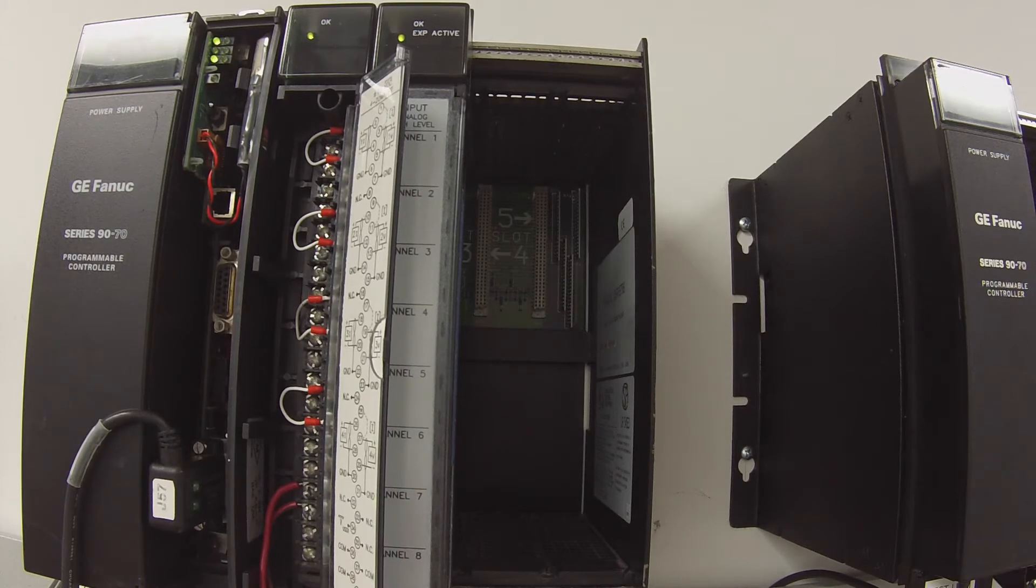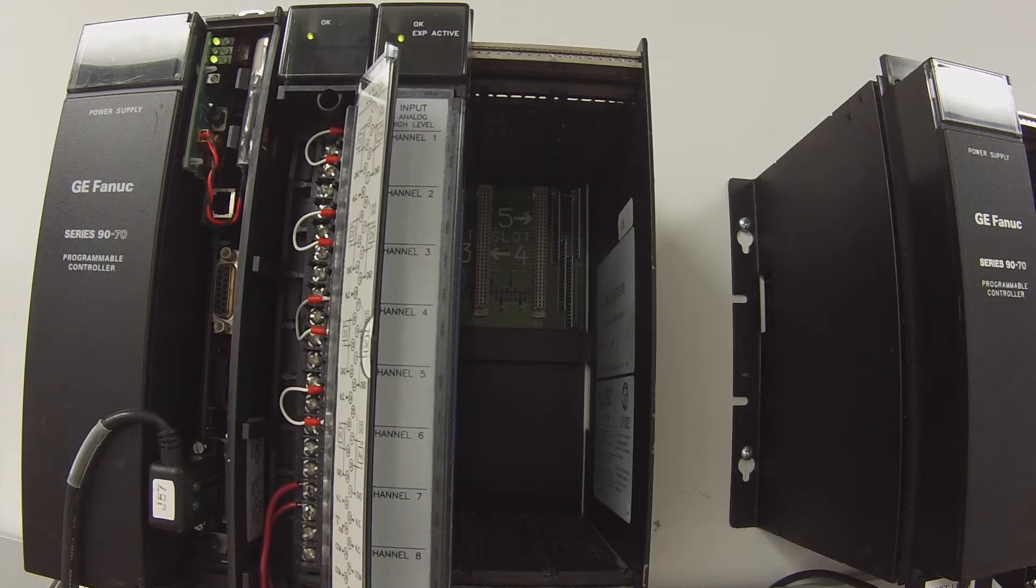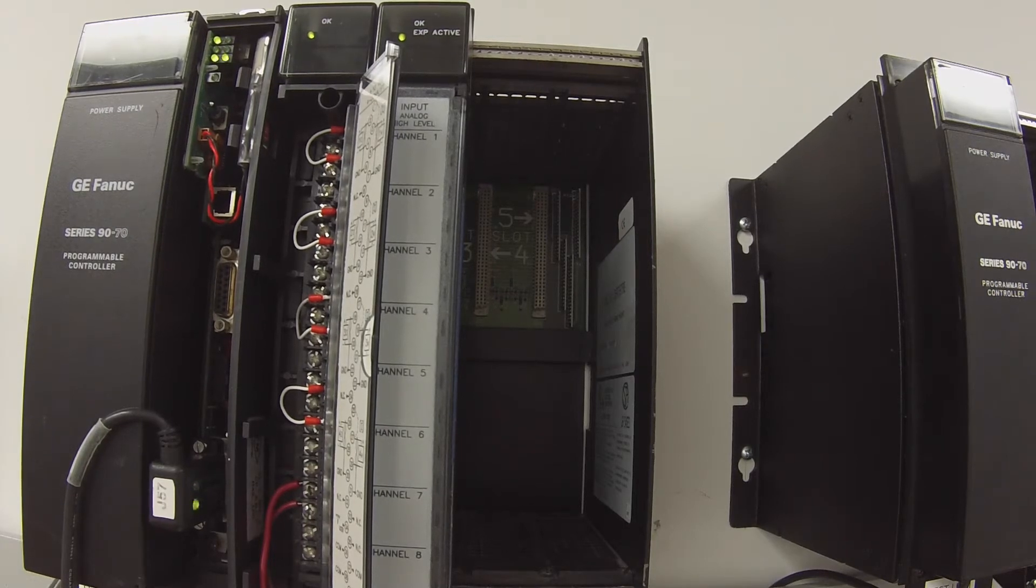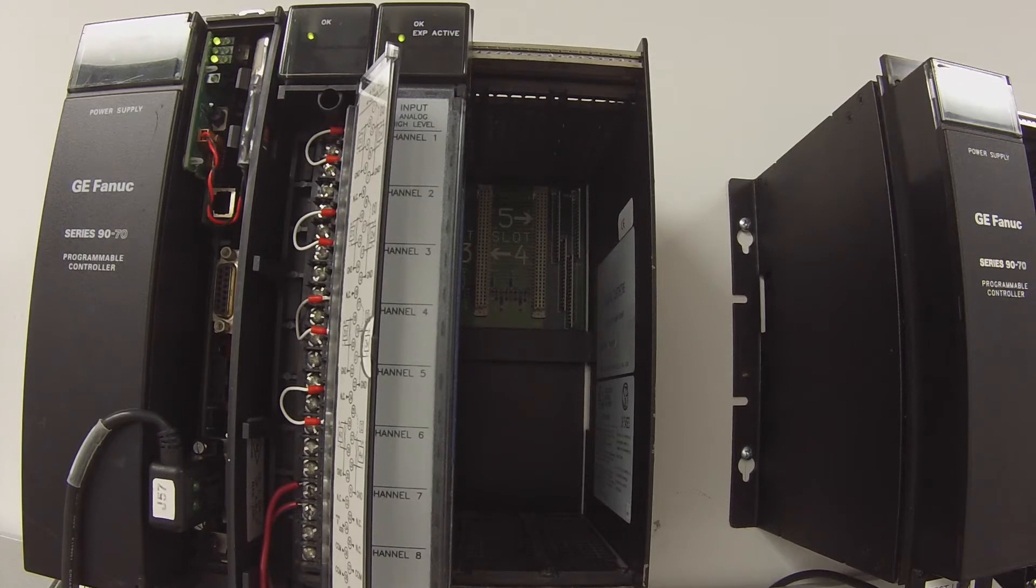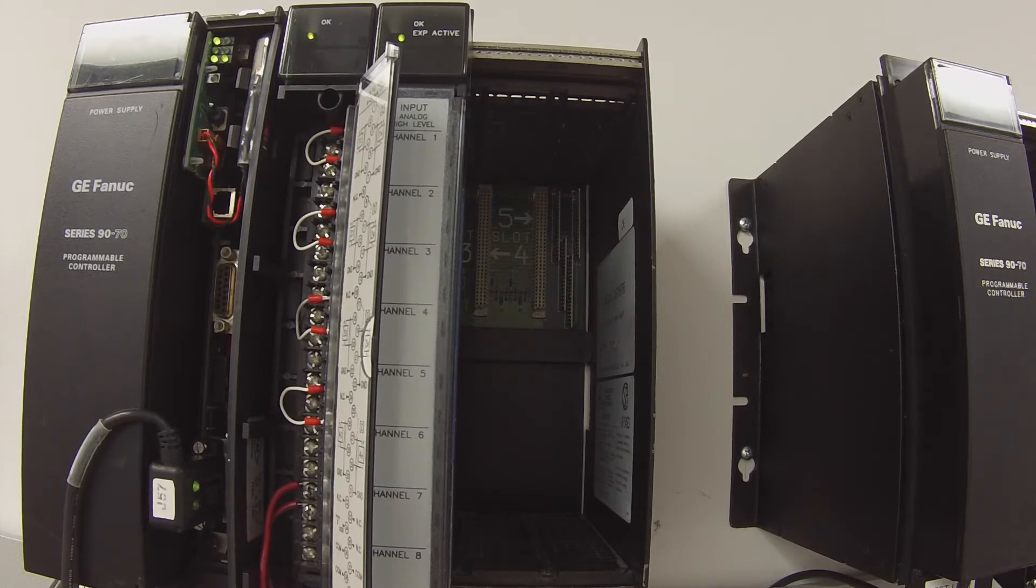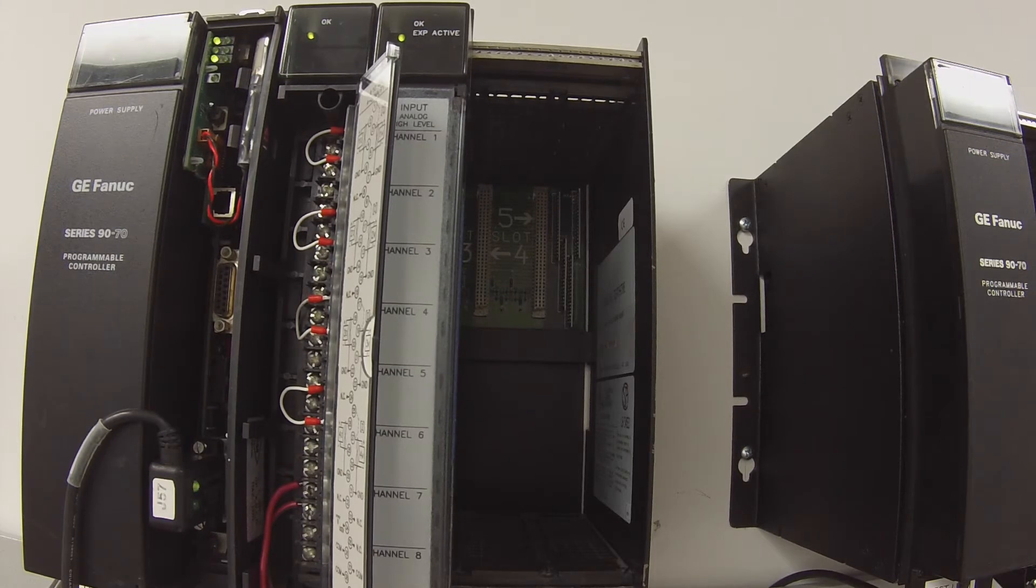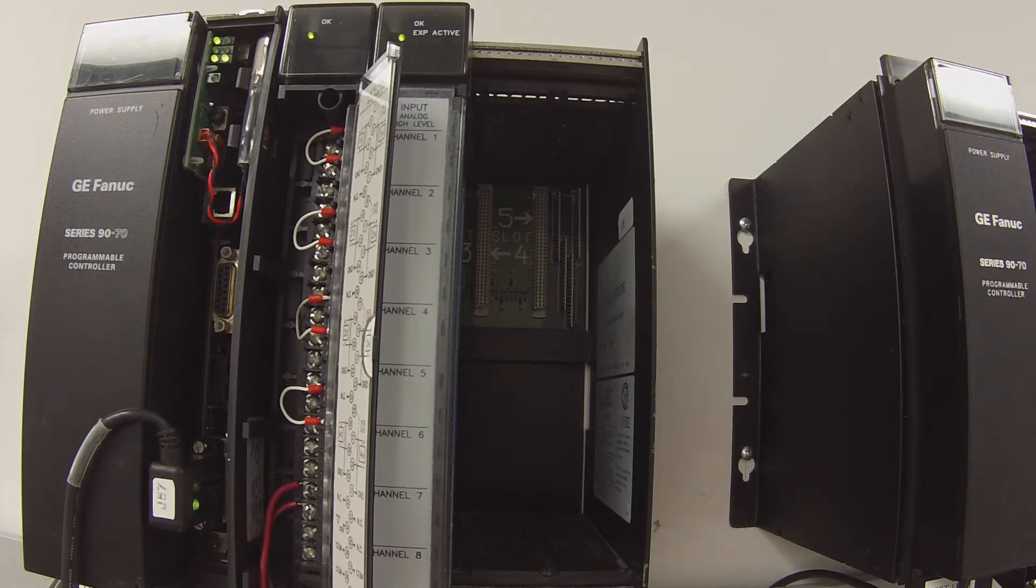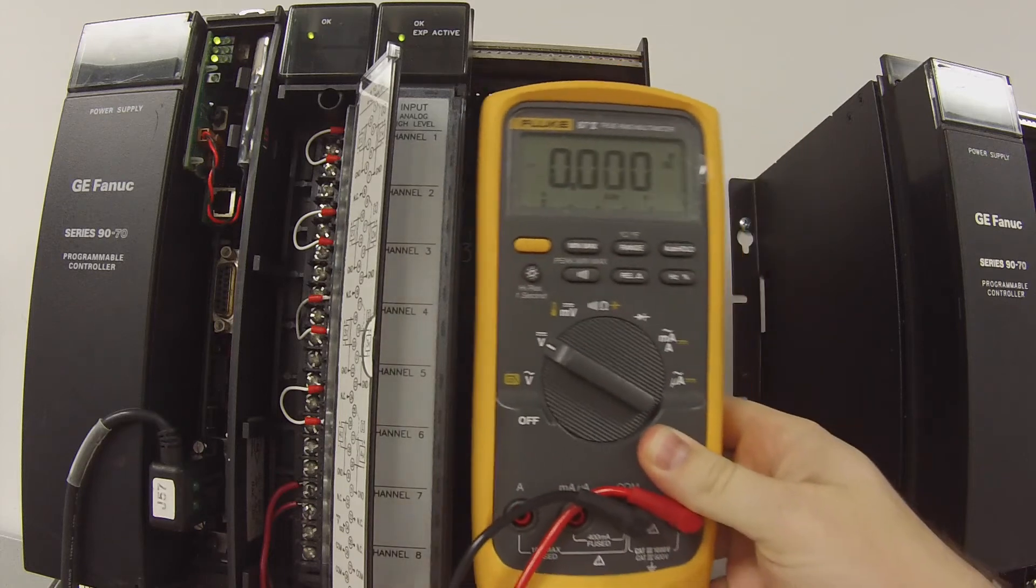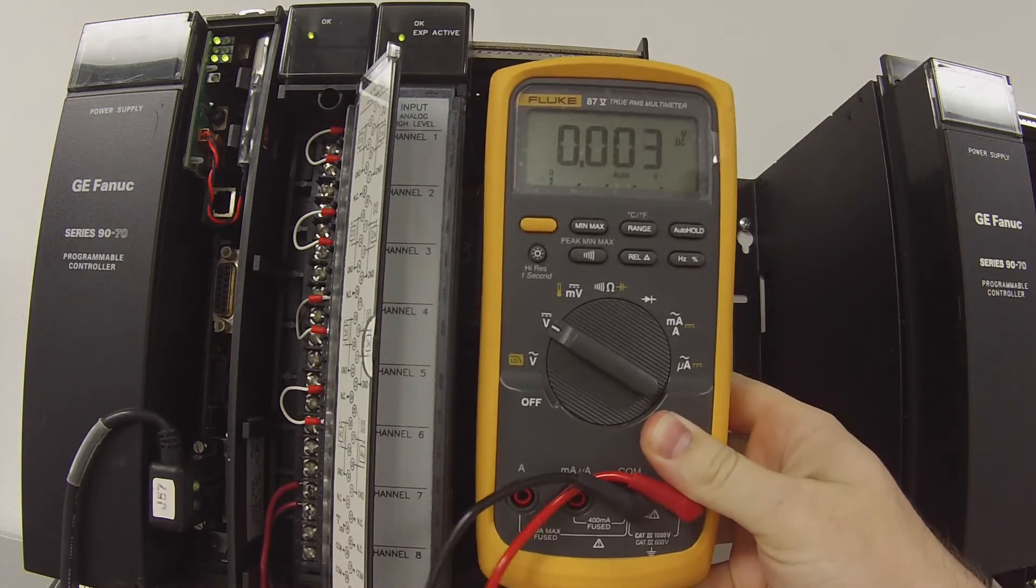We're going to be testing channels 1, 2, 3 and 4. What I usually do is put in the maximum value 32k, 32,000 in each channel, see if I get a full reading, full 10 volts. That's typically like 9.99 volts to a meter. Nothing to be concerned about but that's usually what you want to see.